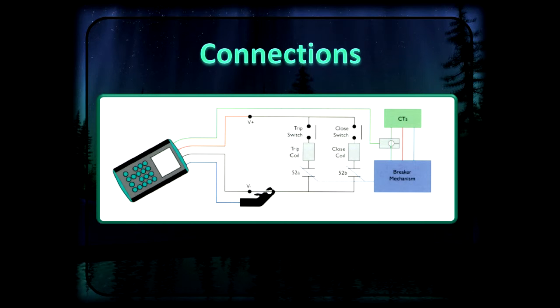Your coils are what operate the breaker and allow it to release its energy to open or release its energy to close. Trip coil, obviously, trips it open. Close coil closes the breaker. And then the green wire goes to your CTs, those are your CTs on the line, so you can tell when all 3 phases actually do open, to make sure that your timing is correct in the breaker.